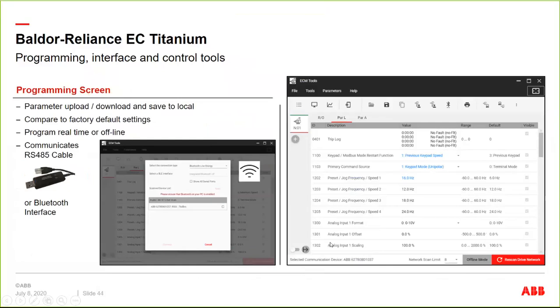So here's what the PC tool looks like. It's a pretty standard PC tool from a setup standpoint. Upload, download parameters, save them to local, etc., and back up your drive. You can program it offline and then connect to a drive and download the parameters that you set up remotely. It does do a comparison between the factory defaults on the right and what's in blue text on the left, so you can see what's been changed.